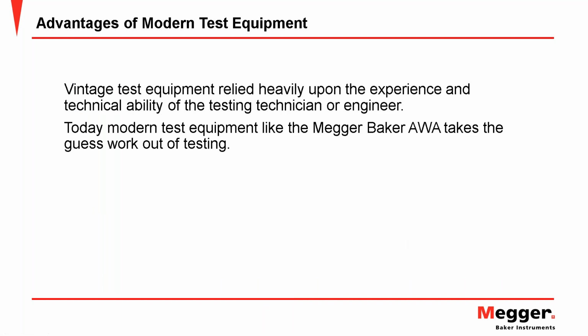So another concern, again, I mentioned earlier, I saw this motor get high potted, and then we went and did the test, and then we went to run the motor and it failed. Oftentimes, older test equipment is to blame for some of those stories, where vintage test equipment relied heavily upon the experience and technical ability of the testing technician or the engineer that was running it to be dutiful, to watch that current level, and if that current level started to take off, maybe we're looking at an analog meter, or maybe some kind of analog digital indication where we see a bar increasing over time, to stop increasing voltage or stop the test, and not necessarily have any kind of active or automated tripping circuit, if you will, or some means of slowing down the test.